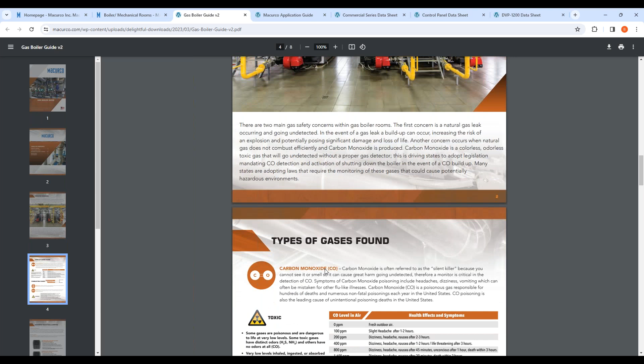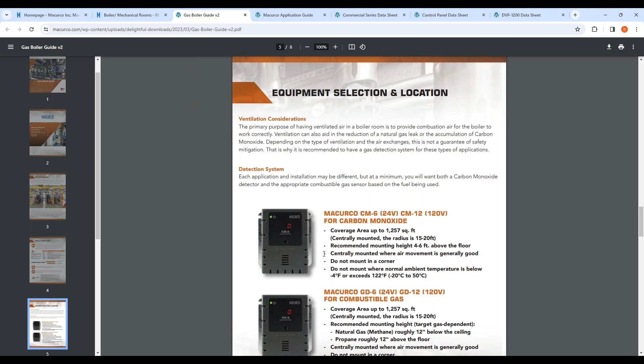Then you get into equipment selection. In each state that we're seeing, the main premise is that at a certain parts per million of carbon monoxide, we are shutting down the boiler. What does that mean? It basically says at a low level alarm, that boiler is going to be shut down. And in most every state we're seeing so far, they're keeping that boiler shut down. It is not restarting. It's not coming back to life because the air got cleaner. It is latched. And what that looks like from a standpoint of a system is pretty straightforward.